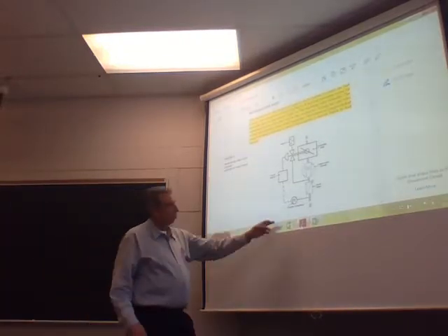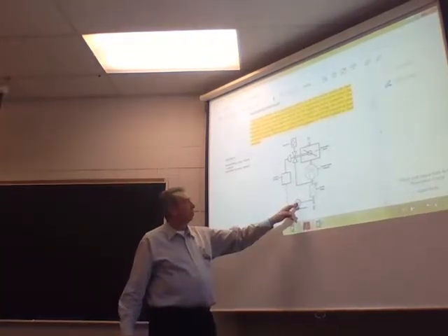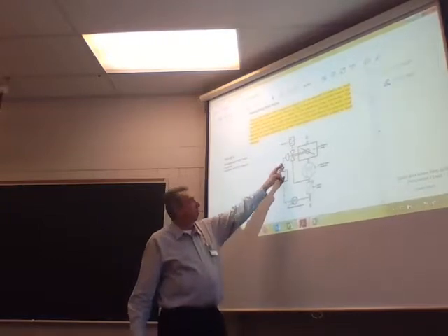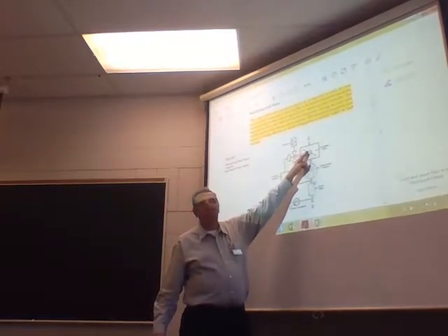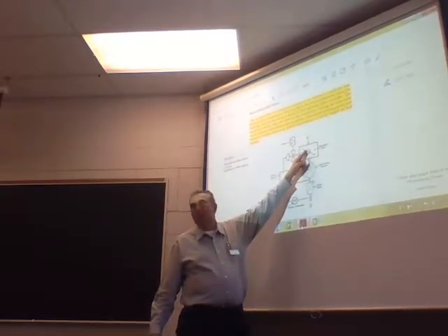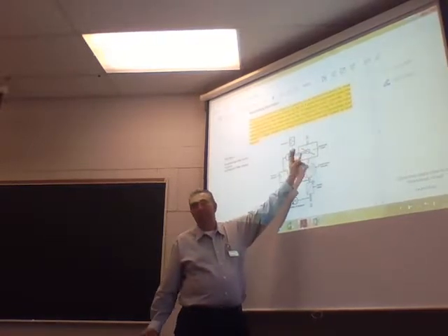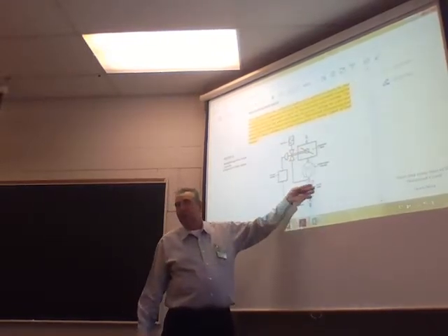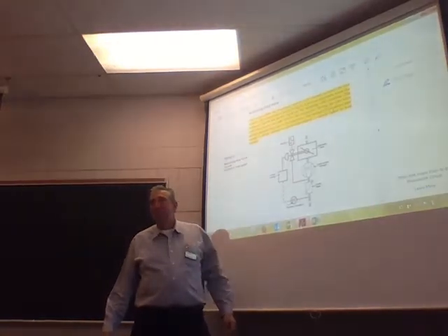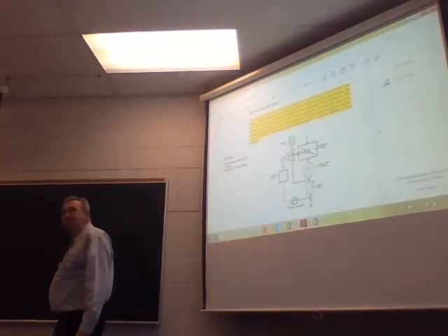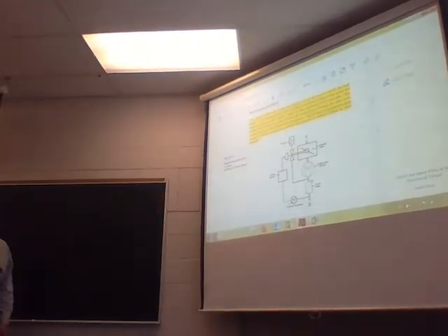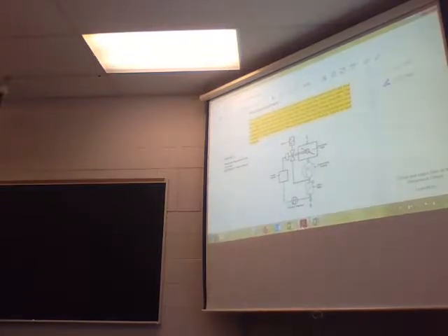So we've got a pressure transmitter. The transmitter goes through a controller, goes to a driver, and opens and closes my valve accordingly to see how much air I need. Cruise control for compressors. Basically, we set it, and as long as our control circuit is set up, she's a good deal.